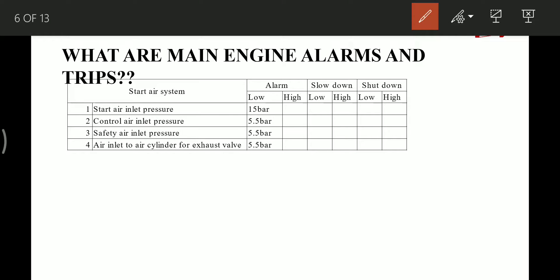The starting air system alarms: start air inlet pressure — low pressure alarm below 15 bar. Control air inlet pressure — low alarm below 5.5 bar. Safety air inlet pressure — set value 5.5 bar. Air inlet to air cylinder for exhaust valve — also 5.5 bar. Below 5.5 bar gives alarm in all three conditions.